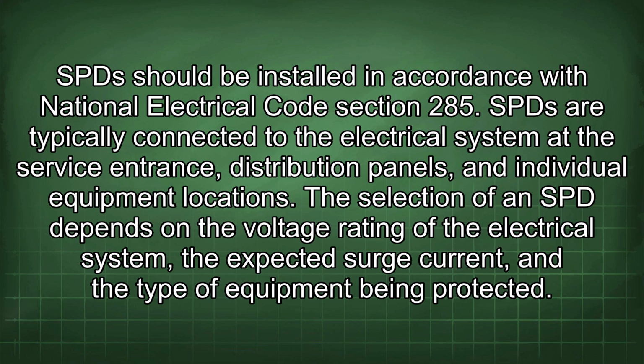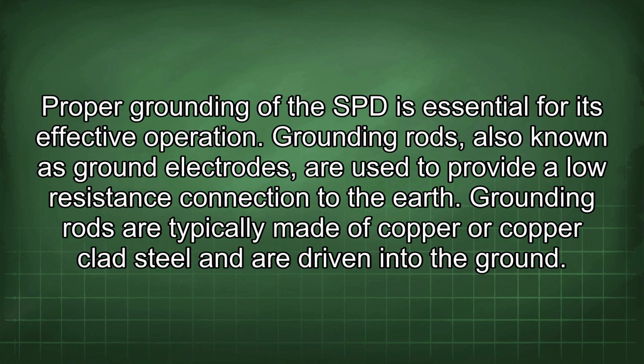SPDs are typically connected to the electrical system at the service entrance, distribution panels, and individual equipment locations. The selection of an SPD depends on the voltage rating of the electrical system, the expected surge current, and the type of equipment being protected. Proper grounding of the SPD is essential for its effective operation.